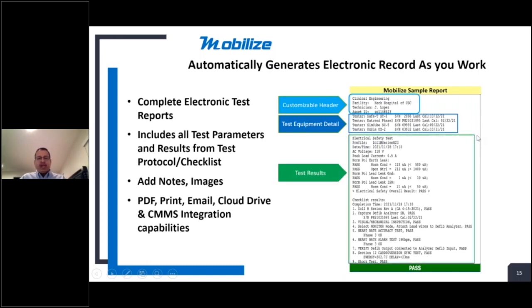And then you have your test results. You have everything that we did. You have here the electrical safety test that was done, the name of the test that we ran, the date and time, the line voltage during the actual testing, current draw of the medical device, and then each an individual test, whether they passed or failed, the test conditions, and then the measured values here in the center. You capture all the measured values. I didn't have to write anything down. I didn't have to do anything to transfer that data.